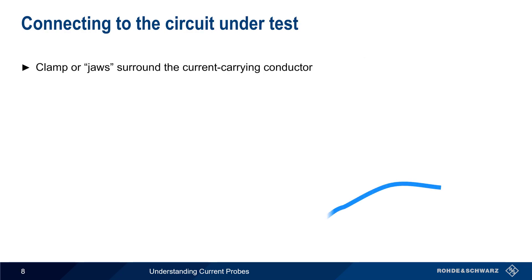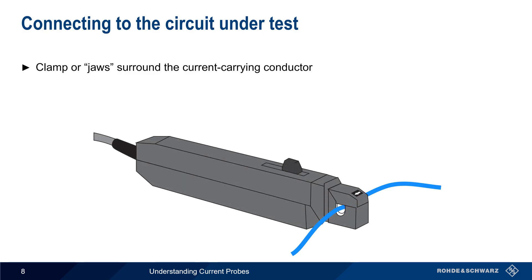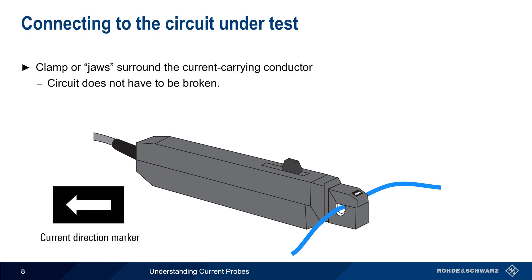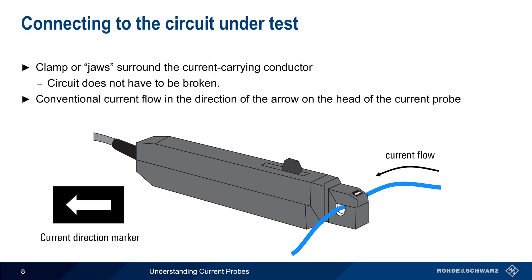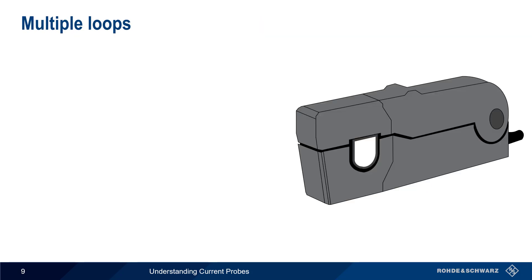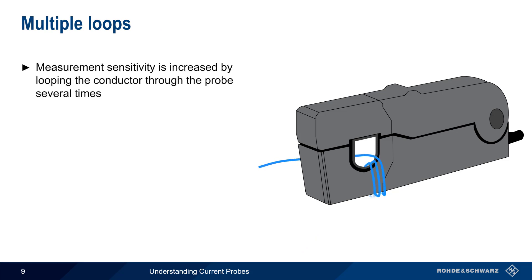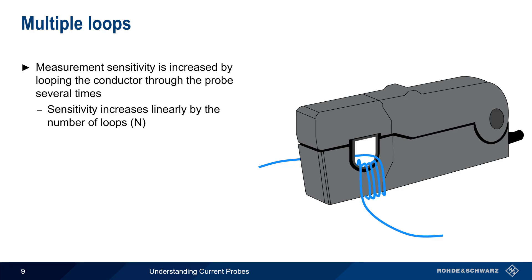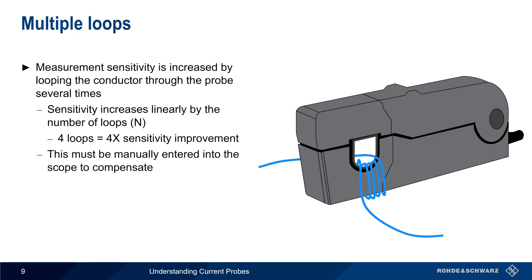Using a clamping style current probe is very simple. The clamp or jaws are opened and then closed around the conductor. Using these clamping or split-core probes has the advantage that the circuit does not need to be broken. Remember that current probes have a direction of current marker — this arrow indicates the direction of conventional, that is plus-to-minus, current flow in the measured conductor. Current probes will still work if connected backwards, but the sign of the measured current will be reversed. One technique to improve measurement sensitivity is looping the conductor through the probe several times; sensitivity increases linearly with the number of loops. Since the scope has no way to know how many times the conductor has been looped, this value must be manually entered into the scope.